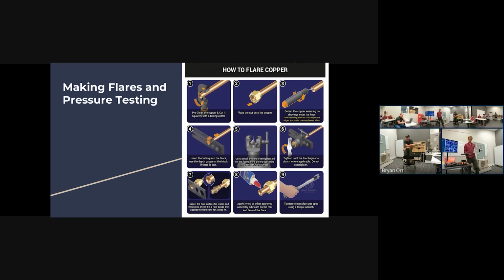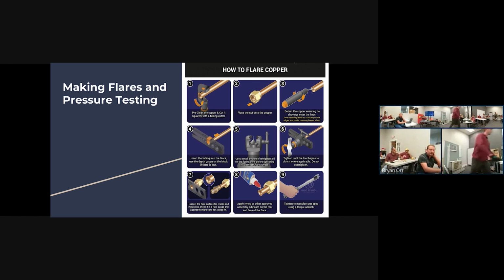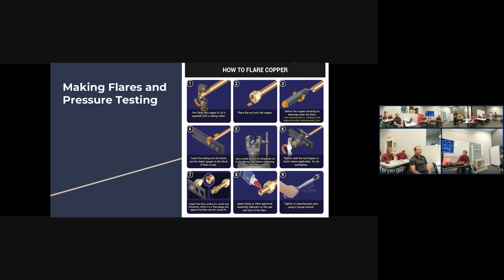It is the better torque wrench, by Hilmor. A couple things to mention: Sam said placing it on the threads of the flare, but really the back and face of the flare are the areas you want the most. A little bit on the threads is okay to act as an assembly lubricant, which is really what we're using it for here, not so much as a thread sealant. A lot of people confuse Nylog with things like True Blue or other thread sealants that harden. That's not what this is. This is not something you're going to buy at Ace Hardware or Home Depot.